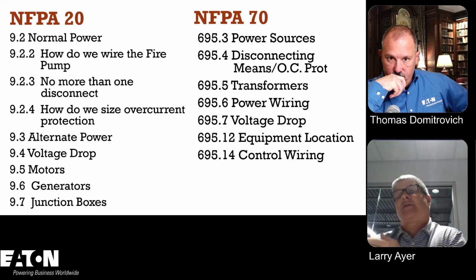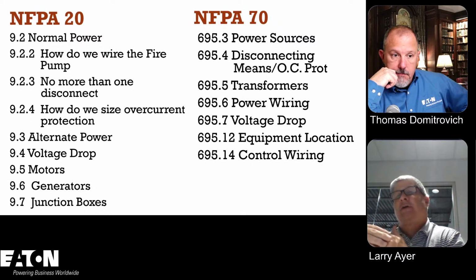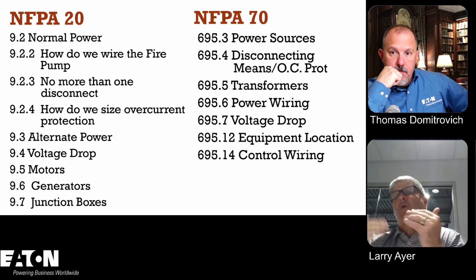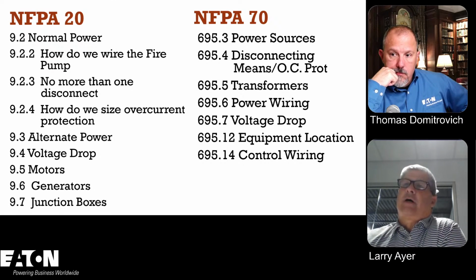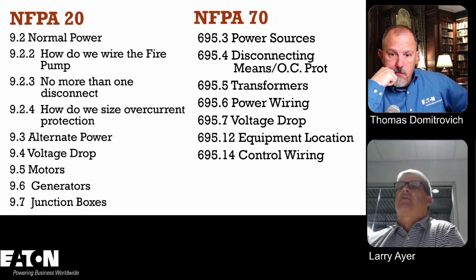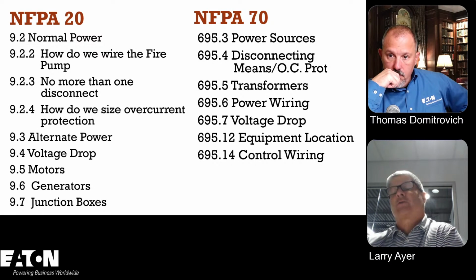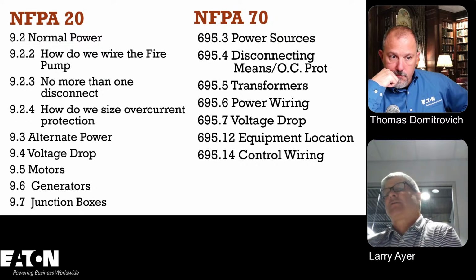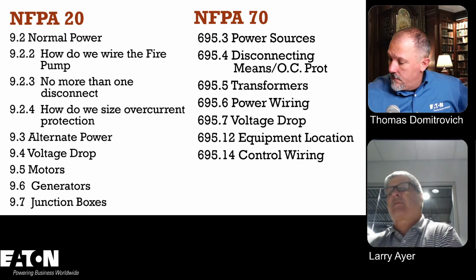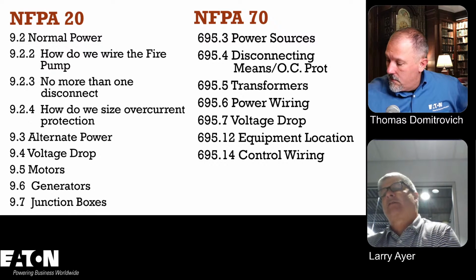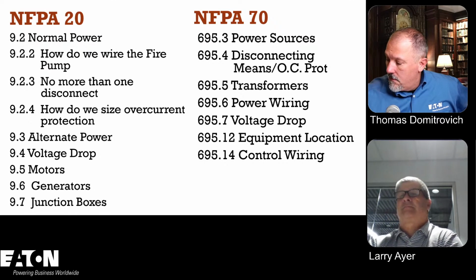If you go to NFPA 70 in Article 695, there's the ones in NFPA 20. There are 5 ways to wire a fire pump. If you go to NFPA 70, some of those 5 ways are kind of sprinkled throughout those requirements. So 695.3 talks about 3 ways to wire a fire pump, and then you talk about transformers, which is another way. So the same information is there. It's just maybe configured a little bit differently.